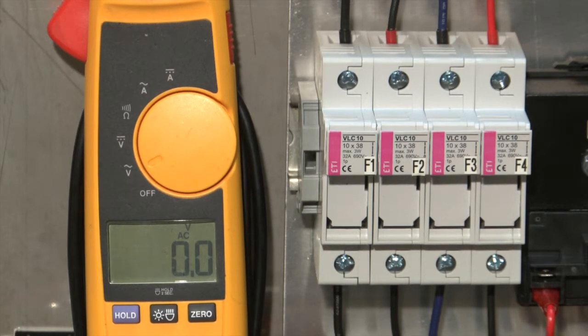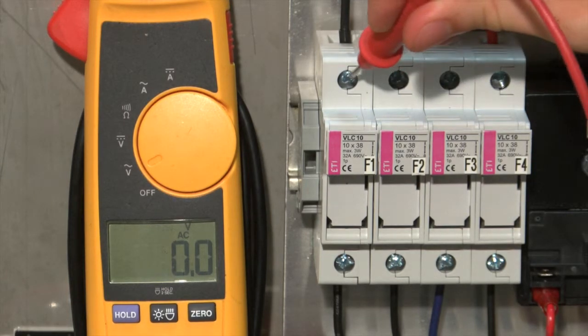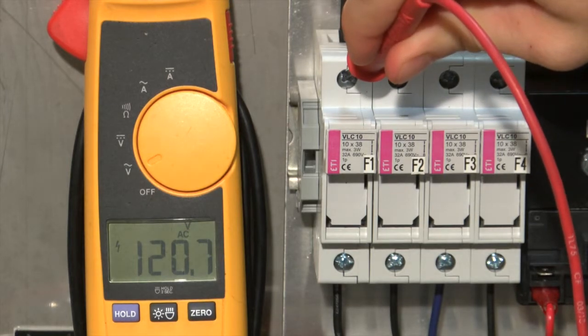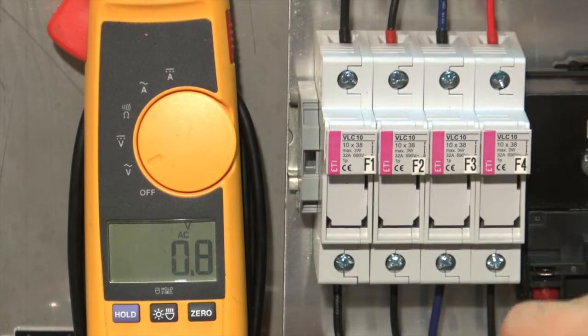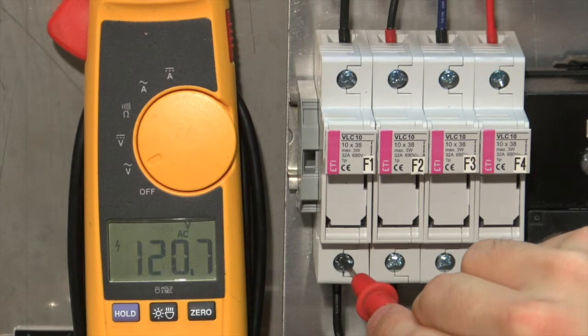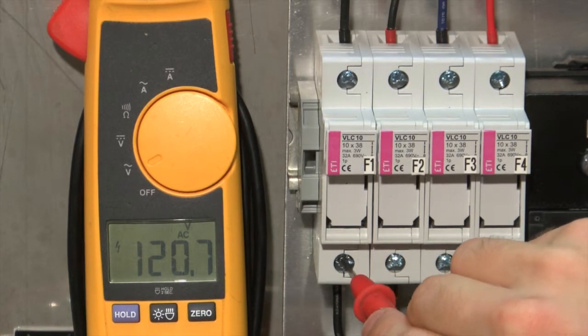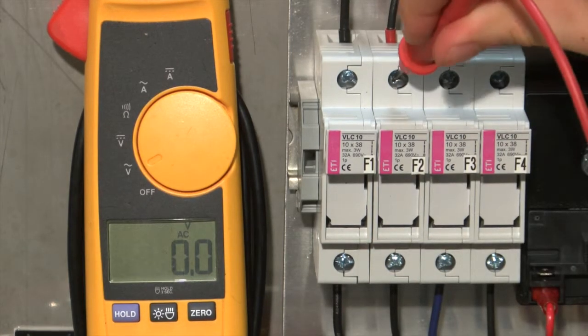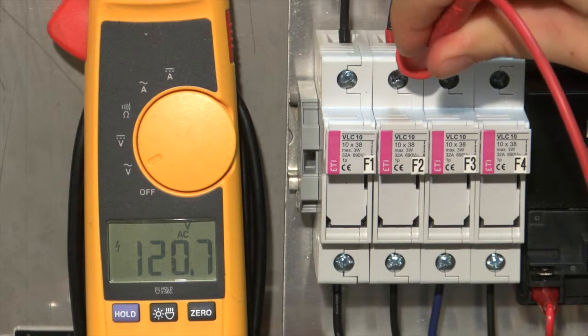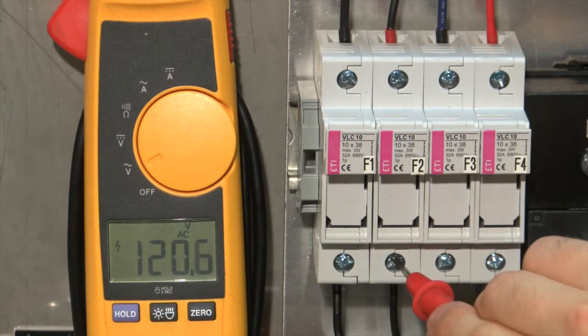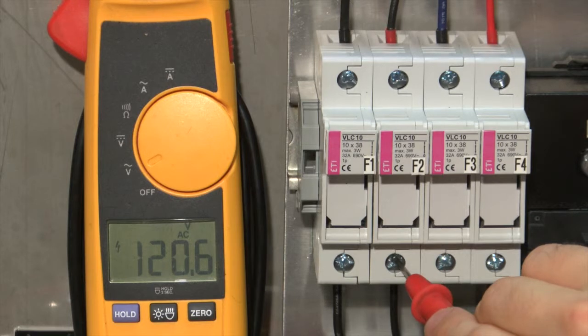To check the 120 volts, we will use one prong on the transformer's neutral on the primary side. Check the incoming power of the fuse is 120. Check the outgoing power of the fuse matches 120. On F2, the incoming power is 120. The outgoing power is 120.